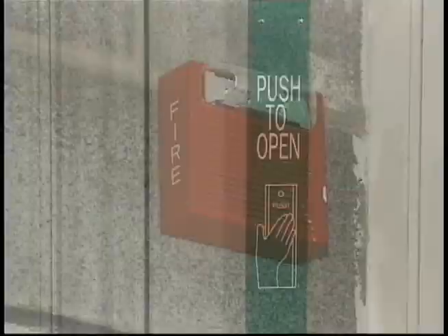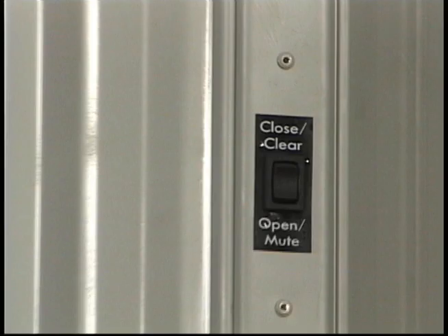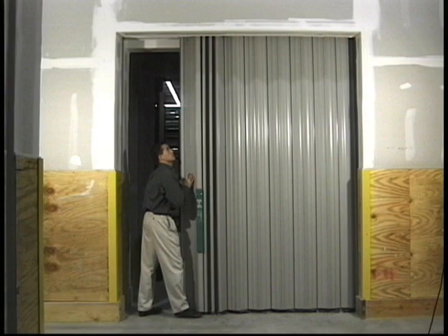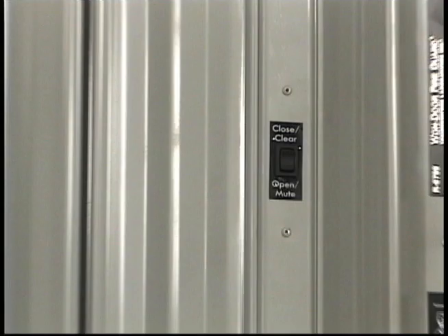If the horn is on continuously, it means the door is in fire mode and will seek the closed position. As soon as the initiating device — smoke detector or building alarm system — has been cleared, the door can be reset out of fire mode by pressing the open close switch. The door can then be opened and stored out of the way by either manually pushing the door open or by pressing the lead post switch to the open position. This alarm cannot be muted. However, if you prefer the door not to sound the horn when in fire mode, contact Won-Door customer service and arrange for a service call. The field technician can program the door to not sound the horn during fire mode.